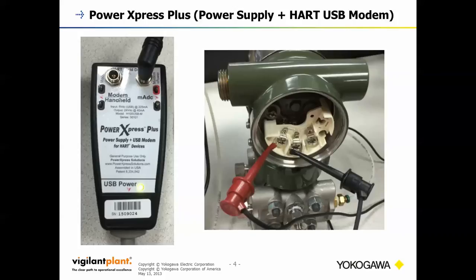So going into a little bit more detail about the modem, this is the Power Express Plus. It's kind of unique in that it provides HART communication modem and power supply for a 24-volt transmitter. So right here there's a little switch, so you can either provide HART modem and the power, or just the modem if that's all you need. Also, they have a couple of IC clip ports for if you want to hook an external handheld like a HART communicator, or like we saw in the previous example with the calibrator, the output of the transmitter. So the milliamp analog output of the transmitter you can measure with either a multimeter or, like in the case before, a calibrator. And then this picture is just showing how the modem is physically connecting to the transmitter via two IC clips on the power supply ports on the transmitter.